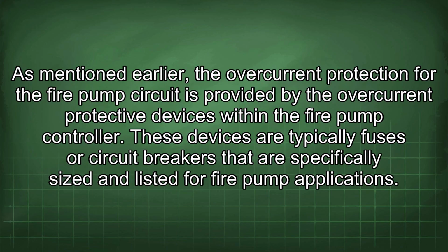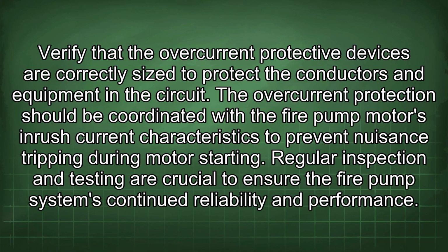As mentioned earlier, the overcurrent protection for the fire pump circuit is provided by the overcurrent protective devices within the fire pump controller. These devices are typically fuses or circuit breakers that are specifically sized and listed for fire pump applications. Verify that the overcurrent protective devices are correctly sized to protect the conductors and equipment in the circuit. The overcurrent protection should be coordinated with the fire pump motor's inrush current characteristics to prevent nuisance tripping during motor starting. Regular inspection and testing are crucial to ensure the fire pump system's continued reliability and performance.